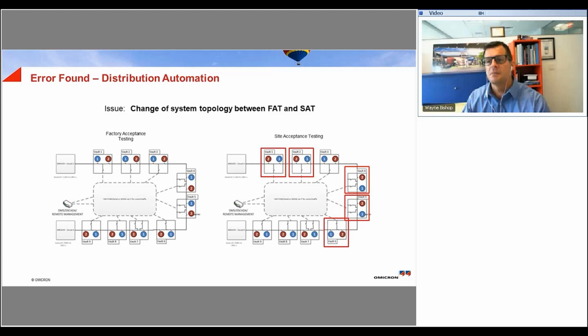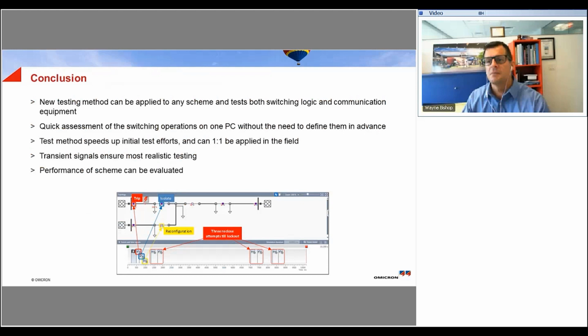So in conclusion, this new type of testing can be used in any kind of DA scheme to test not only the switching logic, but also the communication equipment. The quick assessment, in terms of compiling all of the data and making sure everything is working from our black box approach where we apply inputs and see the outputs, lets us quickly verify whether the correct switching operations did or did not occur.